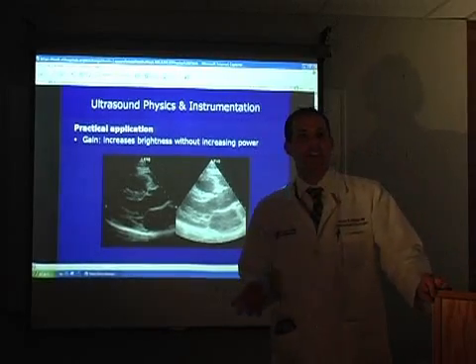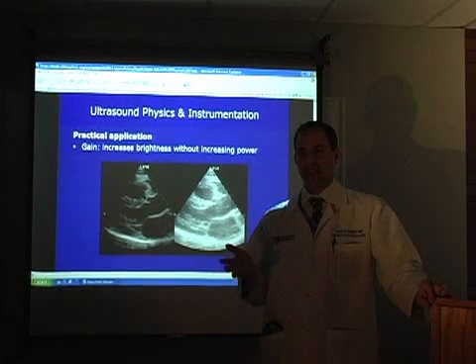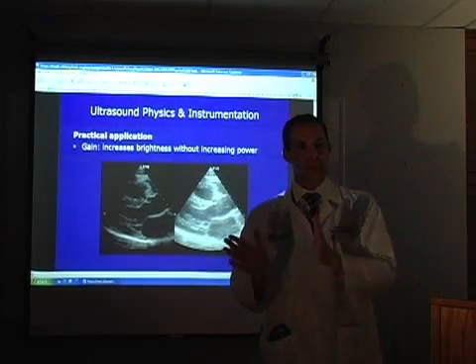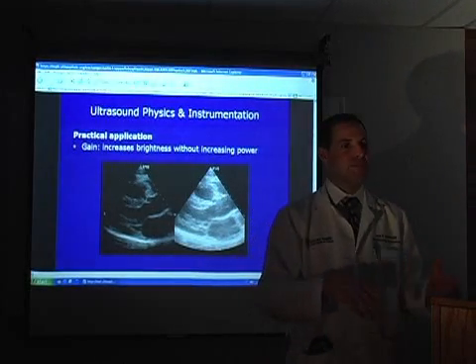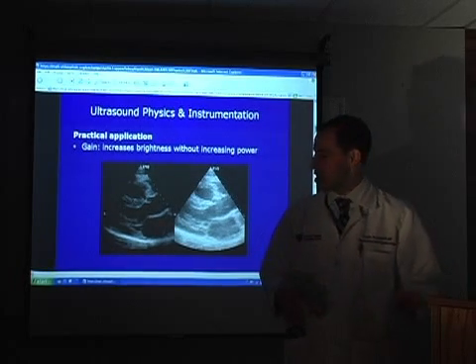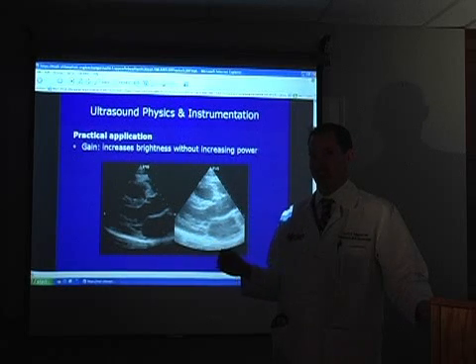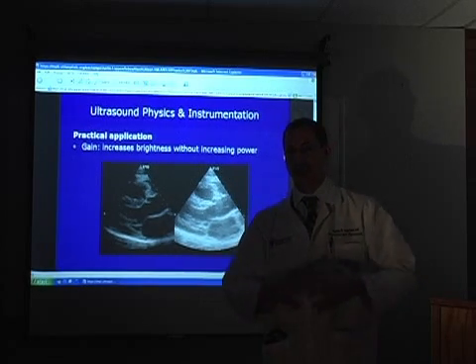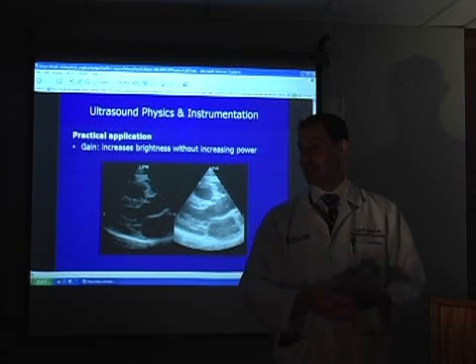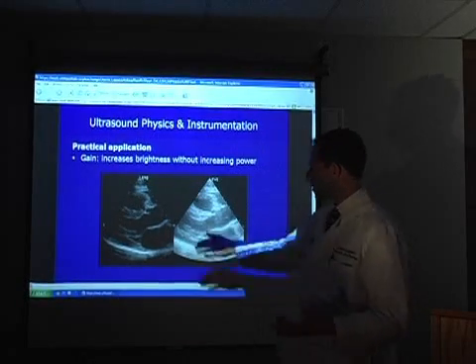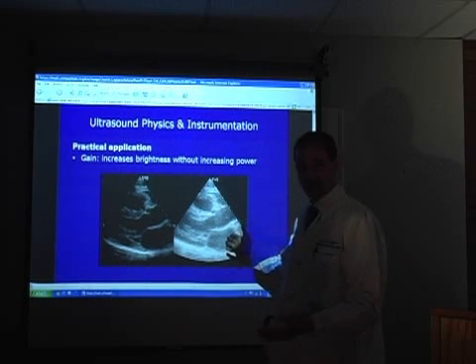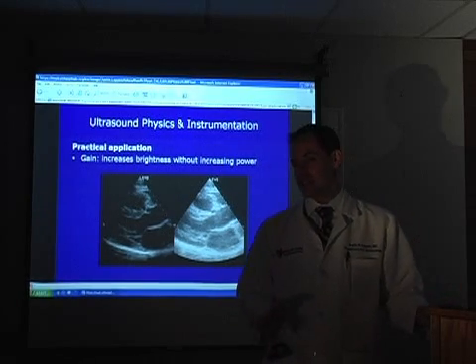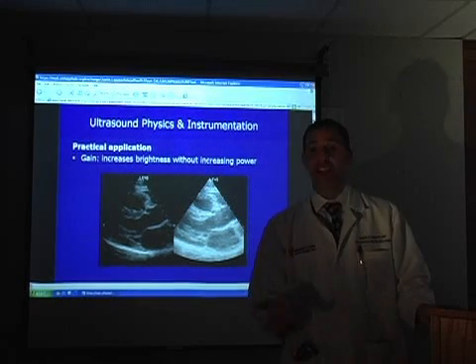Gain adjusts the grayscale — the amount of brightness you see — without changing any of the sound dynamics like power, frequency, or other physics elements. There's usually a knob on the machine for gain. If there's a lot of adiposity or some other scatter or absorption preventing an ideal image, you can adjust the gain. For example, the image on the left may be a little too dark, and a too-bright image is also suboptimal. You want to find the amount of gain that allows you to see what you need, which will differ based on patient characteristics and the target tissue being imaged.